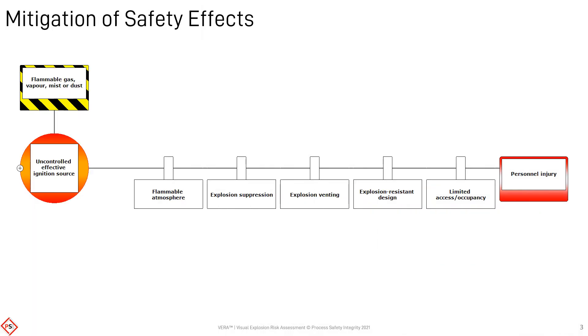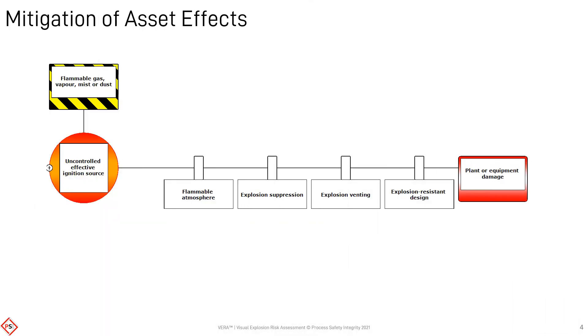If an ignition occurs, the effects may be reduced by suppressing or venting the explosion, or the equipment or structure is designed to be capable of withstanding the impact. Reducing the access to and/or occupancy within a hazardous area may contribute to risk reduction. The impact on fixed plant or equipment is not reduced by access or occupancy, unless they are mobile and only occasionally in the hazardous area.